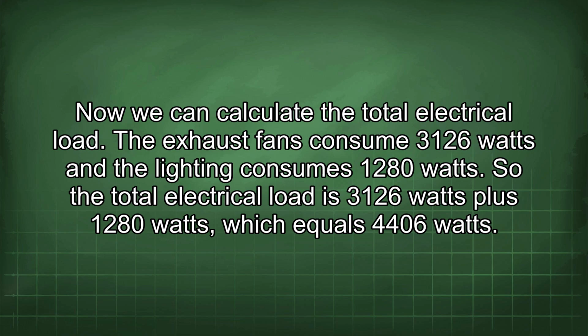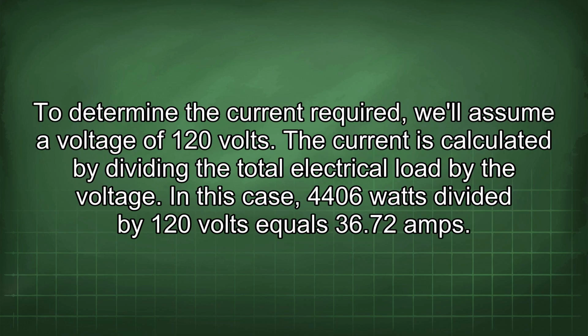So the total electrical load is 3126 watts plus 1280 watts, which equals 4406 watts. To determine the current required, we'll assume a voltage of 120 volts. The current is calculated by dividing the total electrical load by the voltage. In this case, 4406 watts divided by 120 volts equals 36.72 amps.